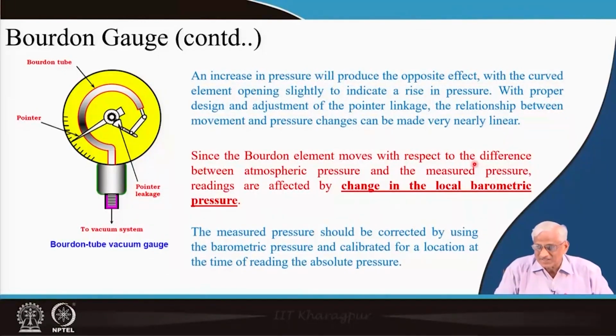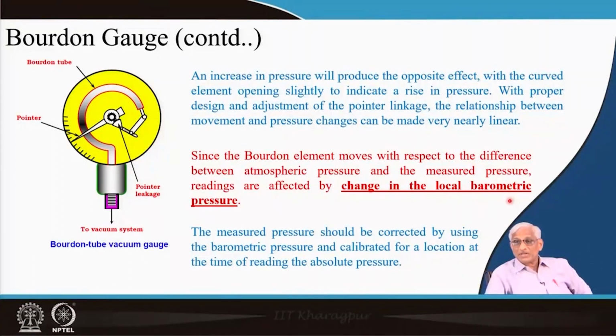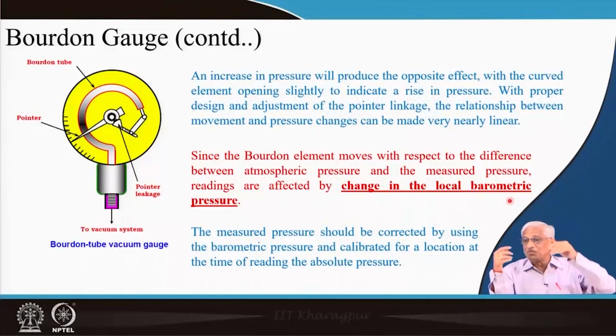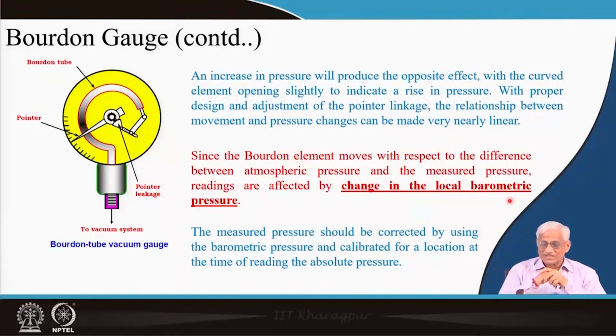This is well understood, there is nothing great about it, it is a simple mechanical gauge. Now, one important point, suppose the local pressure itself is different. If you go to Mount Everest, then the outer surface is also a little partial vacuum, so the deflections will be different. So, you have to have some barometer at the local level, and correct that either in the reading or with some zero adjustment of this gauge. These are done routinely by manufacturers with some additional facilities. So, that has to be done using local barometric pressure corrections. This is one important aspect of it.